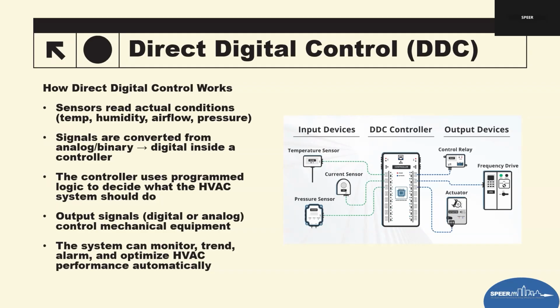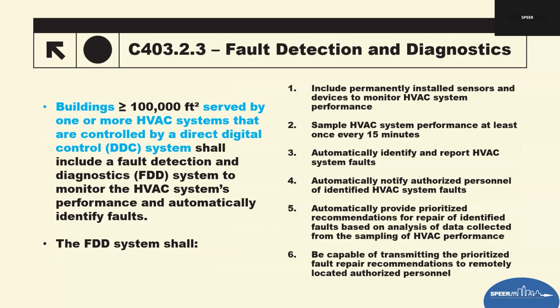So in the 2024, these capabilities tie directly into the newer requirements for DCVs, which include occupied standby, ventilation resets, and also essentially fault detection and diagnostics. In the 21, we had fault detection and diagnostics. Now this is enhancing the DDC control so that these things are real-time and active. They actually push an email to someone when something goes wrong, give recommendations, or can adjust and fix themselves in real time. So to C403.2.3, fault detection and diagnostics.